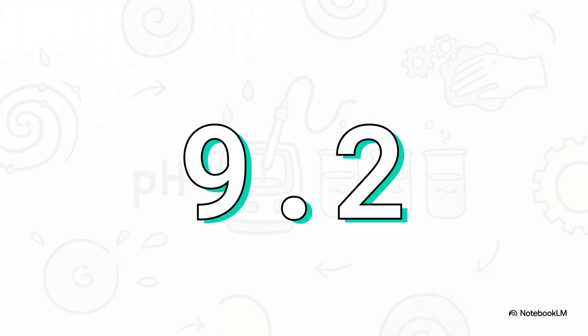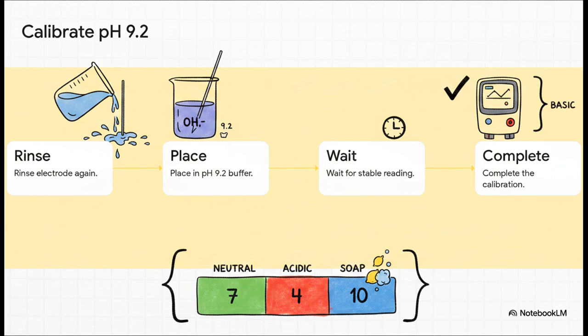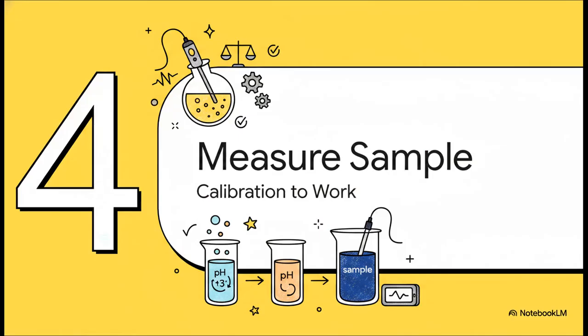Next up, we immediately transition to the total opposite side of the spectrum, to our final basic calibration point, 9.2. The routine here remains absolutely consistent. Do not skip the rinse step with distilled water. Once rinsed, carefully place the electrode into the 9.2 buffer to finalize the instrument standardization. Wait for that stable reading, and complete the calibration. By strictly following this exact sequence, neutral, acidic, basic, you've now successfully bracketed the entire pH scale that your samples might possibly fall into.